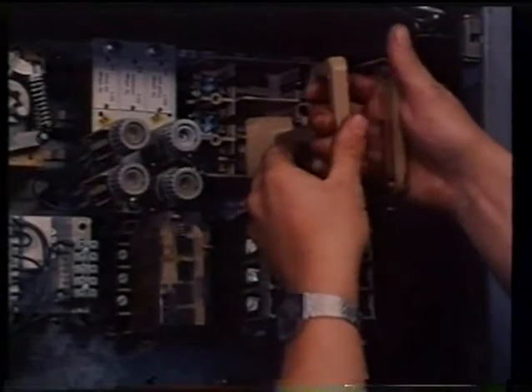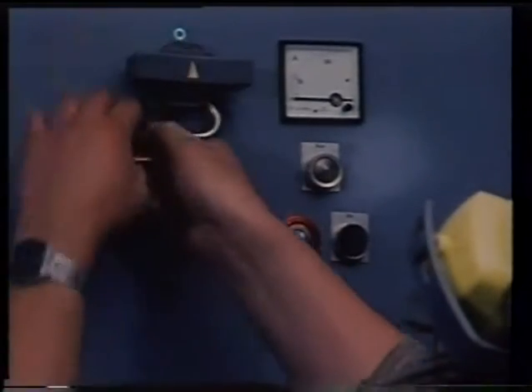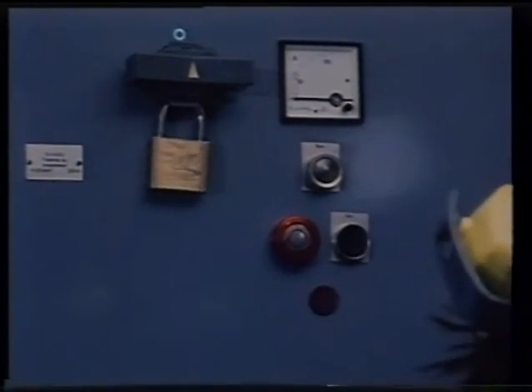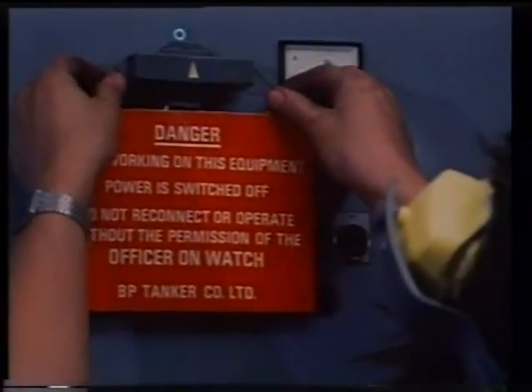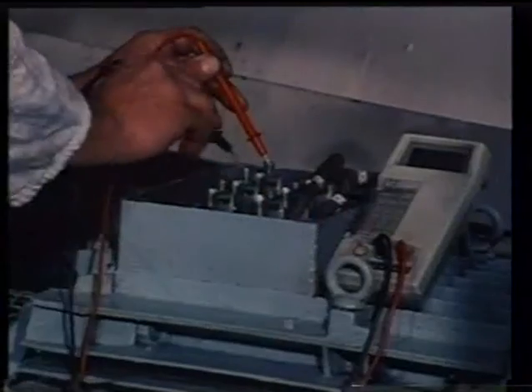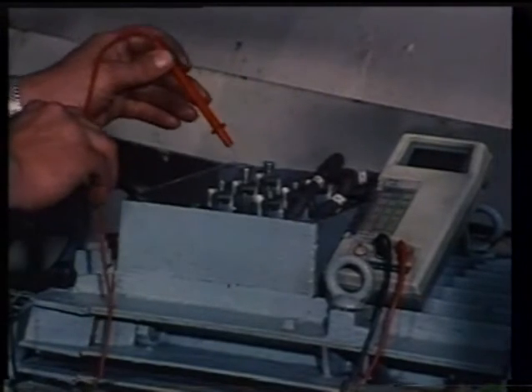Now, we must emphasize electrical safety. The golden rule is, before any work is done on an electrical installation, first isolate the circuit by removing the supply fuses or locking the circuit breaker in the open position so that the circuit cannot be energized accidentally. Then post a warning sign to alert others that the circuit is being worked on. Then prove the circuit dead with a voltmeter or an approved line tester. A switchboard can never be considered dead unless all AC generators connected to it are stopped, locked off, and all other supplies are disconnected. These points can never be emphasized strongly enough. The electrical rescue procedure is described in Programme 1 of this series.